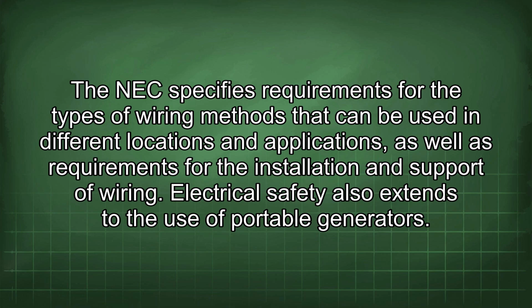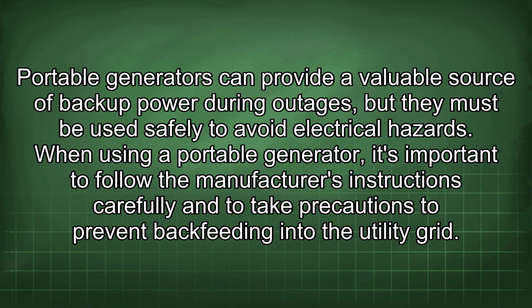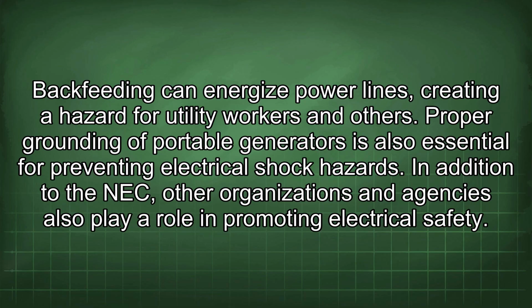Electrical safety also extends to the use of portable generators. Portable generators can provide a valuable source of backup power during outages, but they must be used safely to avoid electrical hazards. When using a portable generator, it's important to follow the manufacturer's instructions carefully and to take precautions to prevent backfeeding into the utility grid. Backfeeding can energize power lines, creating a hazard for utility workers and others. Proper grounding of portable generators is also essential for preventing electrical shock hazards.